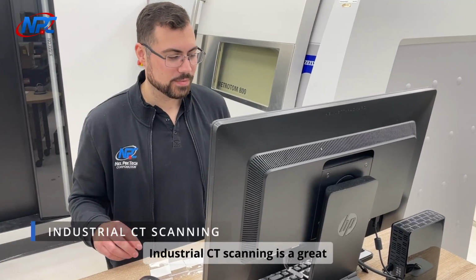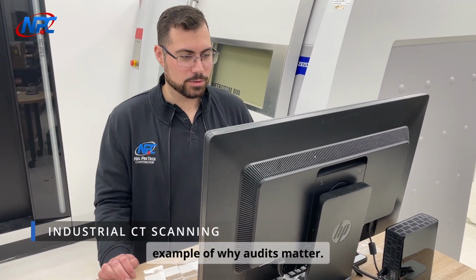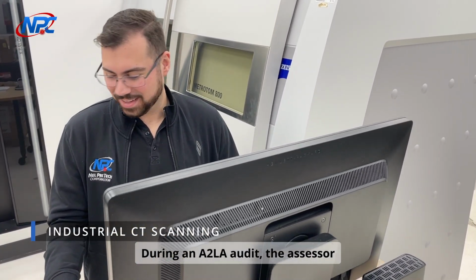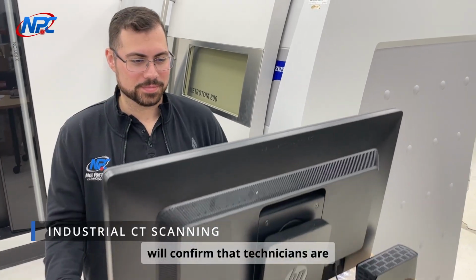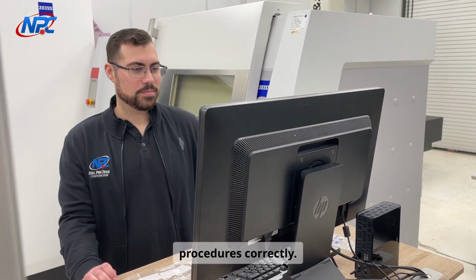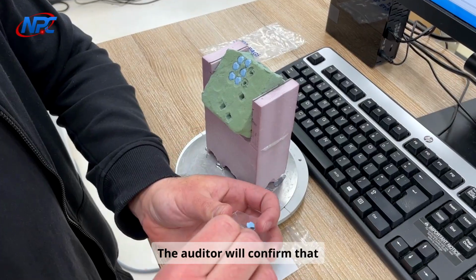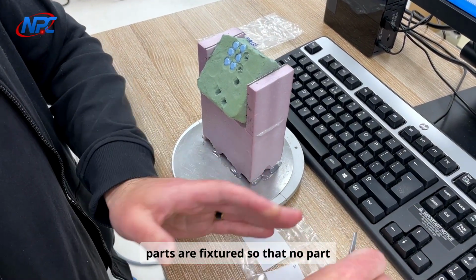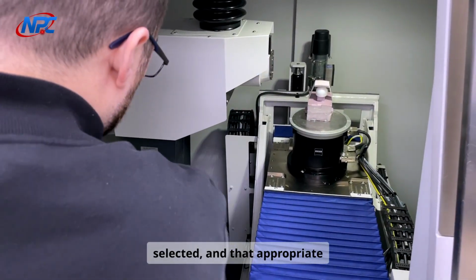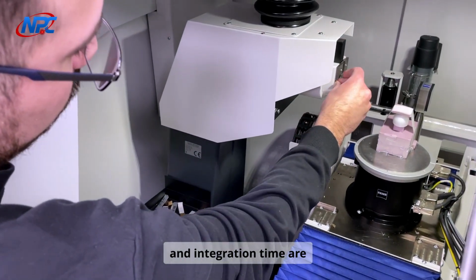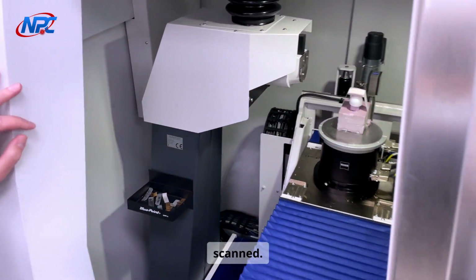Industrial CT scanning is a great example of why audits matter. During an A2LA audit, the assessor will confirm that technicians are following measurement procedures correctly. The auditor will confirm that parts are fixtured so that no part movement occurs during measurement, that the correct filtering is selected, and that appropriate settings such as voltage, current, and integration time are appropriate for the part being scanned.